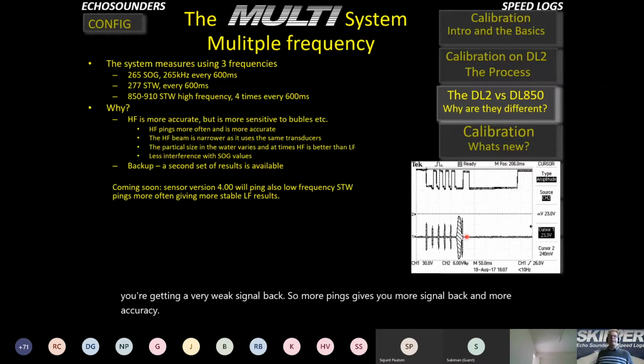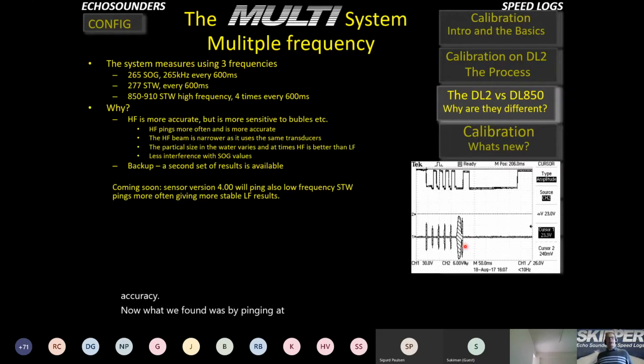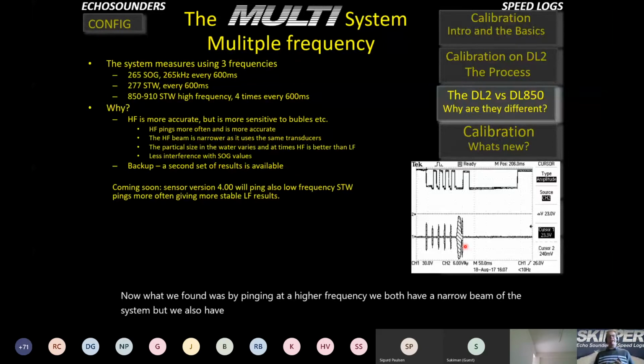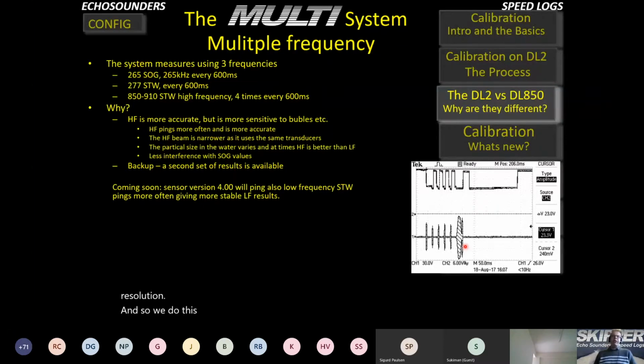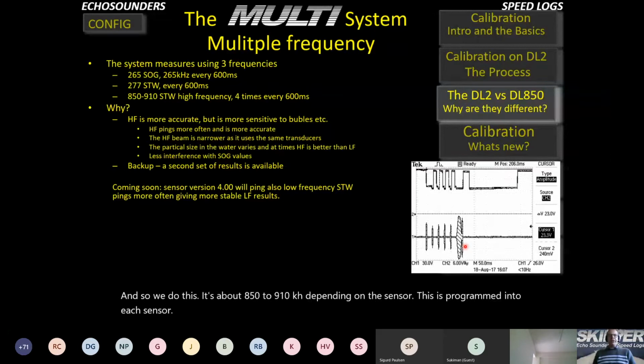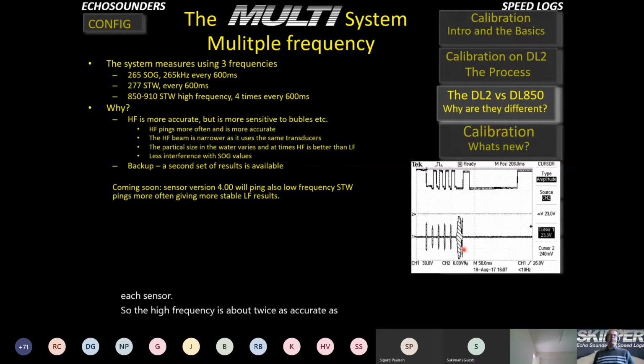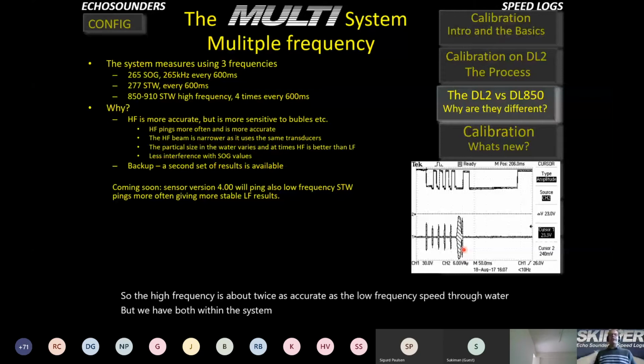Now, what we found was by pinging at a higher frequency, we both have a narrower beam of the system, but we also have a better accuracy because the higher frequencies tend to have better resolution. And so we do this at about 850 to 910 kilohertz, depending on the sensor. This is programmed into each sensor. So the high frequency is about twice as accurate as the low frequency speed through water, but we have both within the system. So one is redundant to the other.